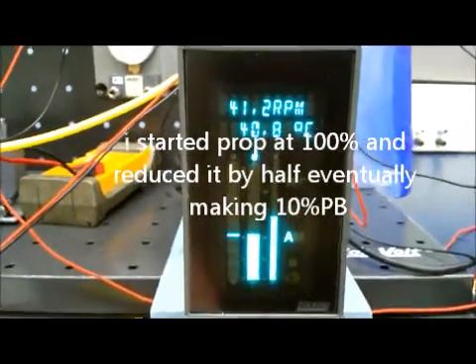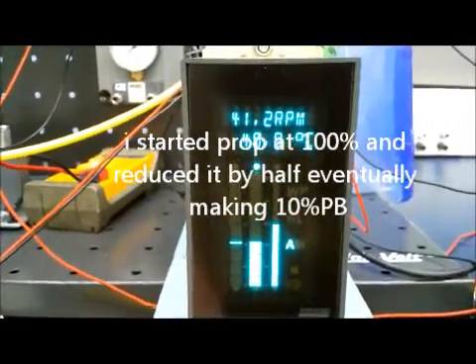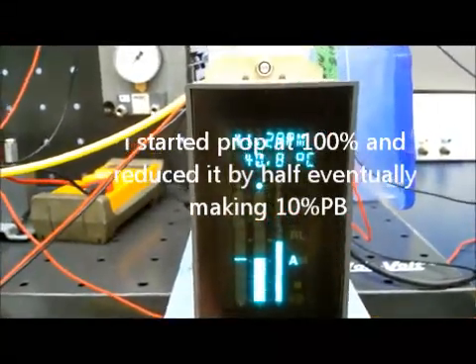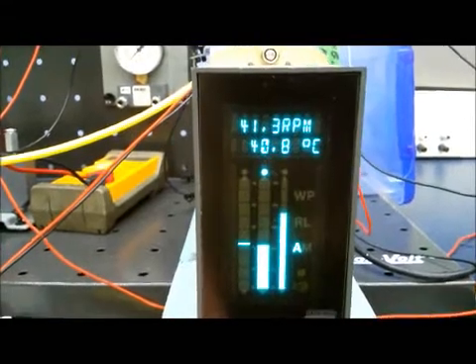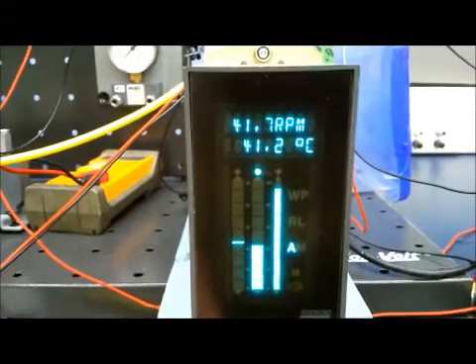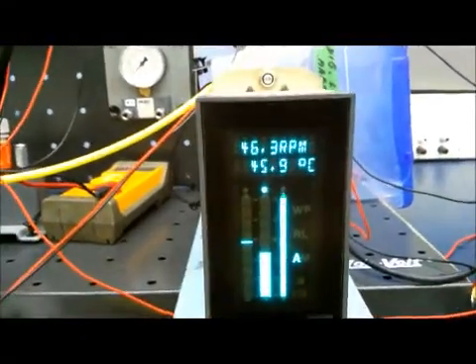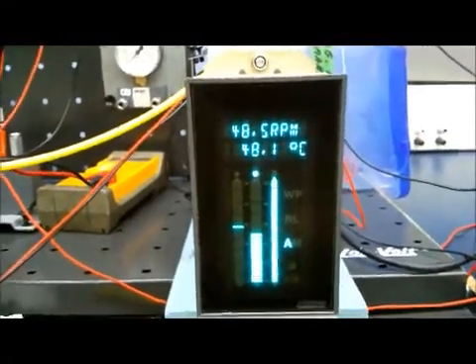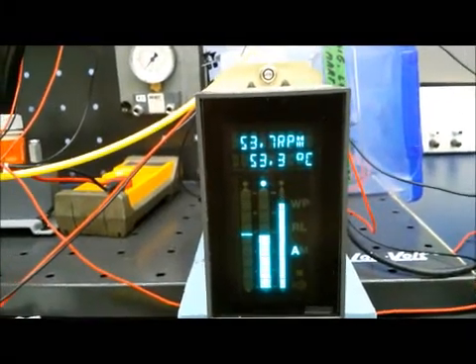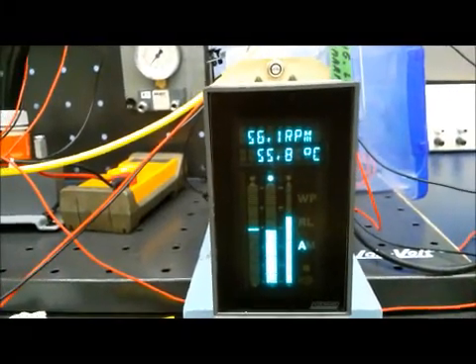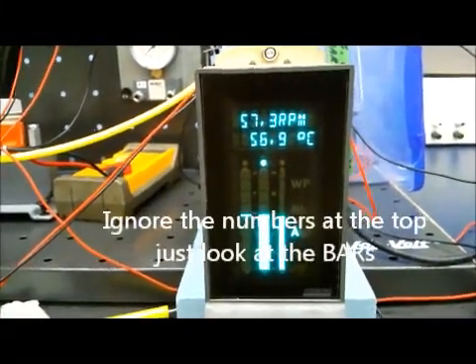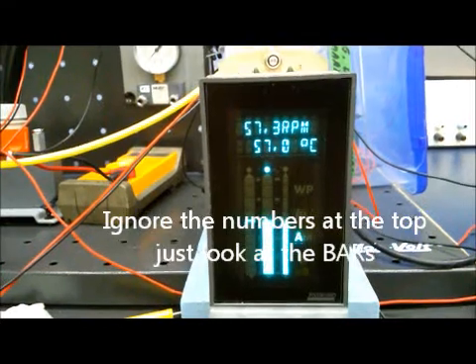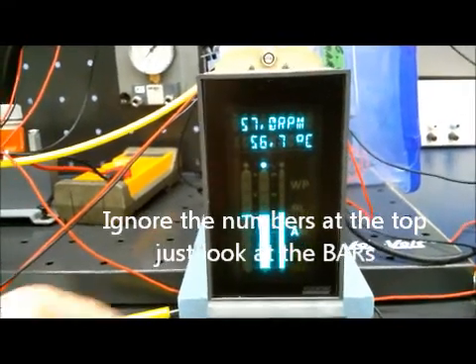I'm going to make a step change and we'll watch it respond. I'm going to change it by 20%. There's approximately a 20% change, and there's my level catch up. Just watching the middle bar. No oscillation and it was nice and quick.